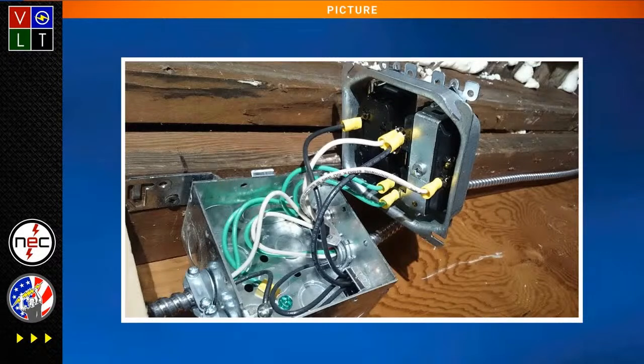I'll be honest, I just installed a contactor and I used them. It was number 10 stranded wire, and I felt it was a better connection to use number 10 stranded wire with those fork terminals onto the contactor than to just put the stranded wire underneath the terminals. If it would have had a clamp style, like a vise style compression, I probably would have just landed the conductor directly underneath the contactor. But I just felt it was a better install to use those fork terminals, and I feel you can make that judgment call. The inspector thought it was fine, so I passed. It wasn't like they're going to fail you for stuff like this.